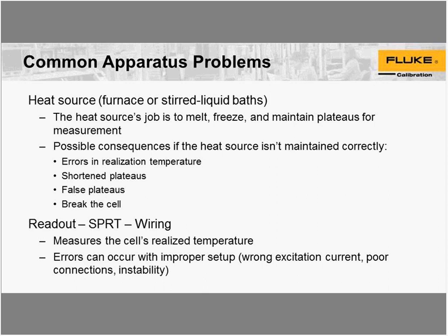The apparatus, if set incorrectly, can also cause shortened plateaus or false plateaus. And then, of course, there's a scenario where it could actually break the cell. I wouldn't say it's a fairly common thing, but we do have a lot of folks who don't monitor the uniformity of their furnaces, and they end up breaking cells. And I'll show you here an example of how the uniformity of the furnace.